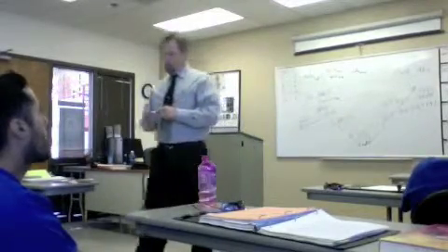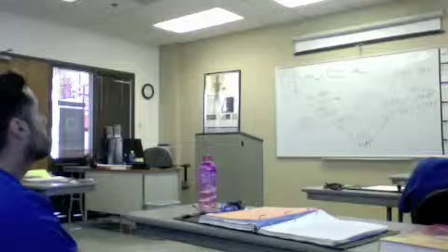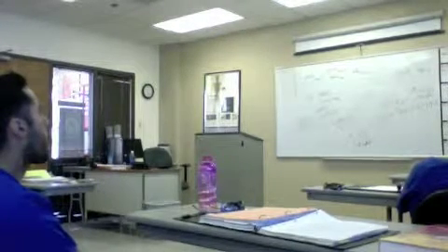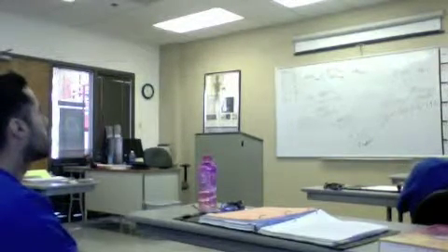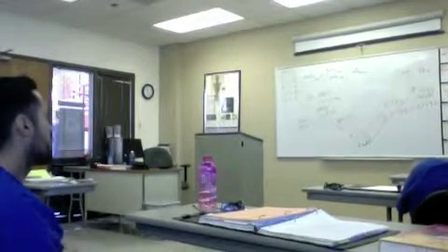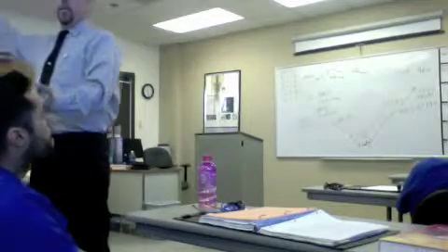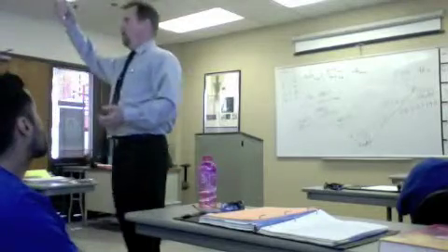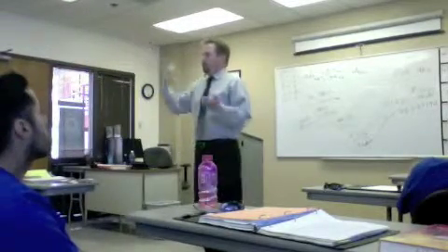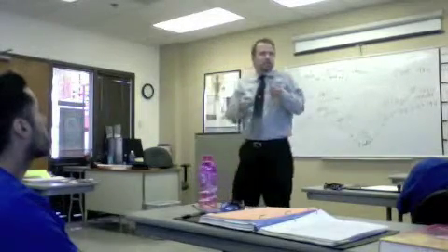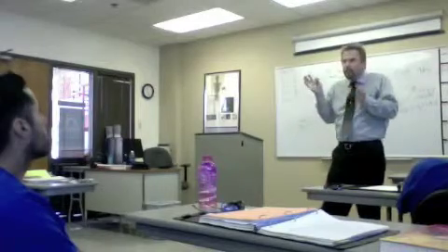Question? When you drop the grid ratio, doesn't that decrease contrast? You have to adjust the kVp to compensate for that. You want the same contrast. We usually don't. For simplicity, I could use 75 kVp on everybody in this room. We know the lower the kVp, the bigger the range of mAs. Somebody petite, 20 mAs, up to 800 mAs I've used. When it was with chest, 110 kVp I could use on everybody in here, but it's only like 2 to 8. It's a very small range.